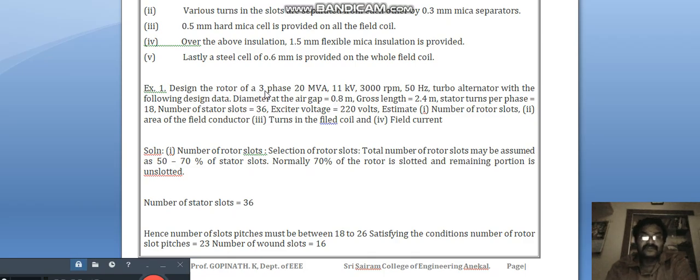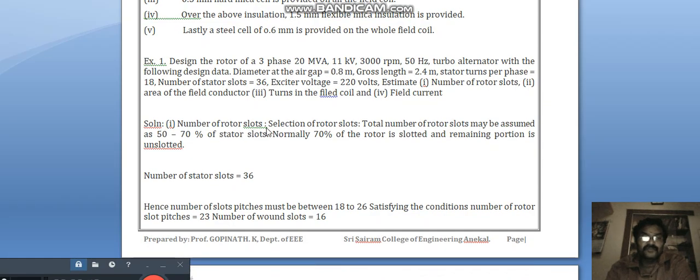Example: design the rotor of three-phase turbo alternator with the following data. Solution: number of rotor slots, selection of rotor slots. Total number of rotor slots may be assumed 50 to 70% of stator slots. Normally, 70% of the rotor slots is slotted, remaining portion is unslotted.